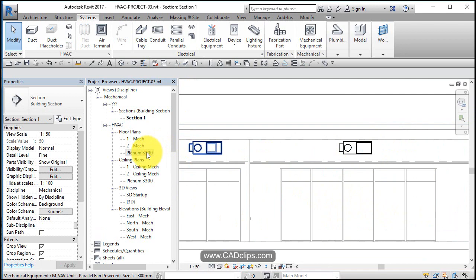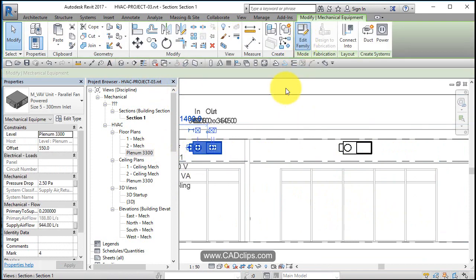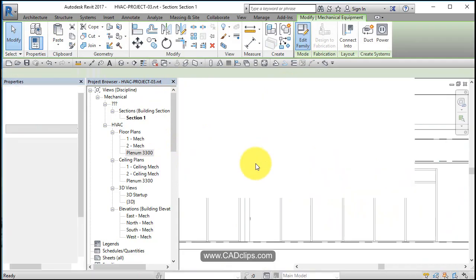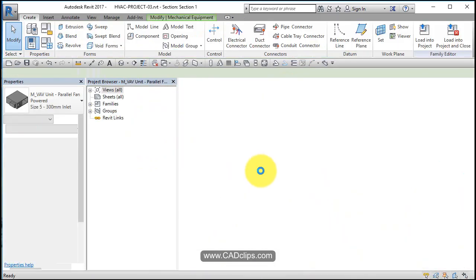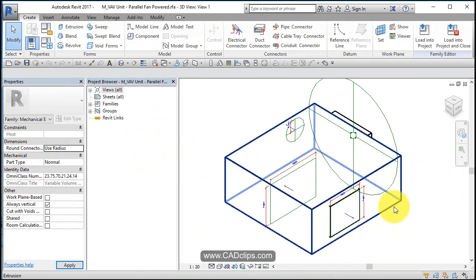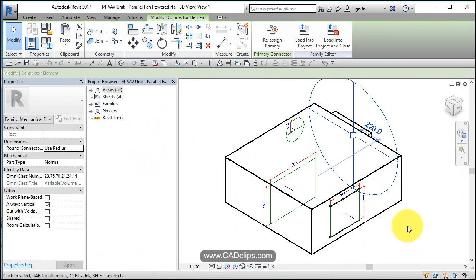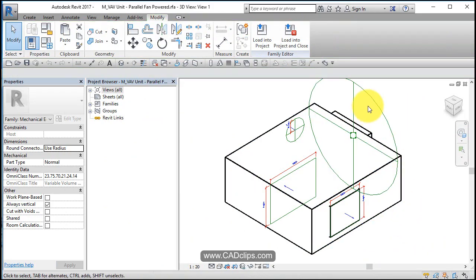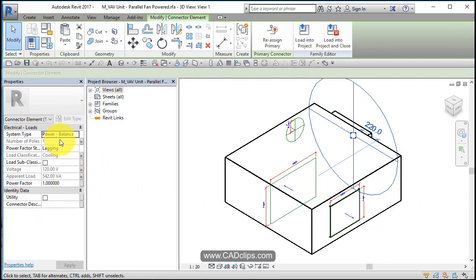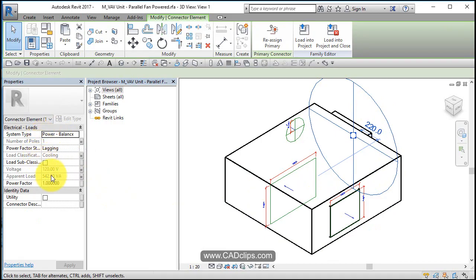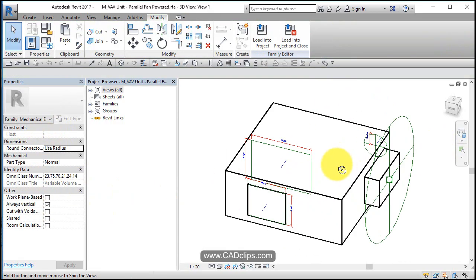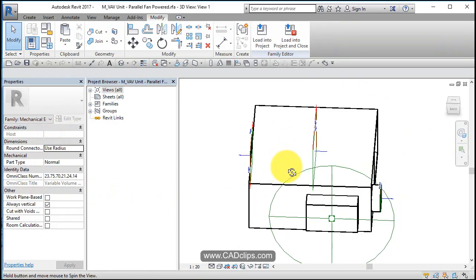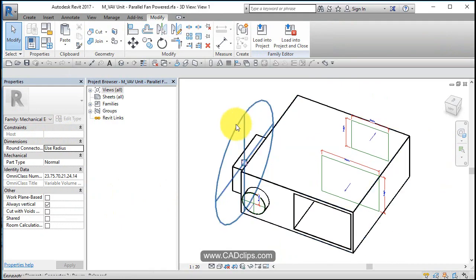I always open up these families to see what's in there so let's pick on this family and say edit family. So this is our mechanical equipment okay and these are the connectors. These are what's important. When you click on this connector it's going to tell you what system type, what classification it is, and a lot of the juicy information. This is the intelligence of that piece of mechanical equipment. So we've got, if you click on here, it's a connector element power balance so it's a power balance connector.